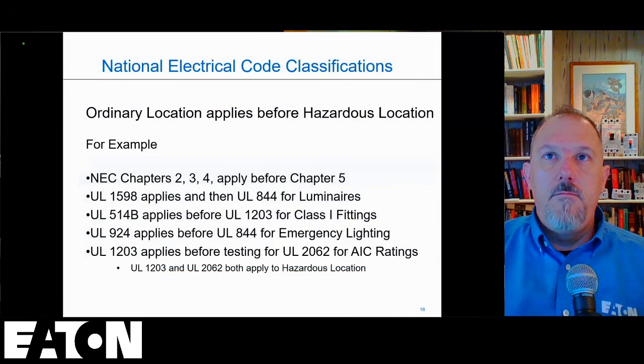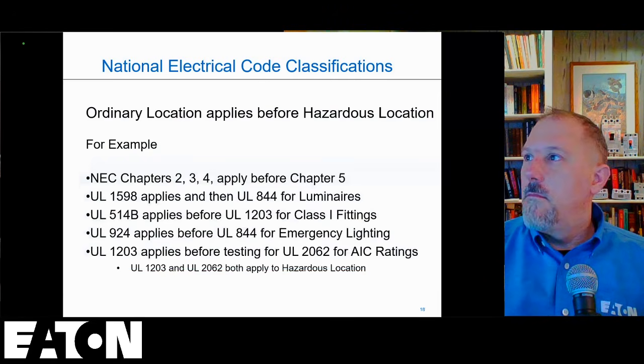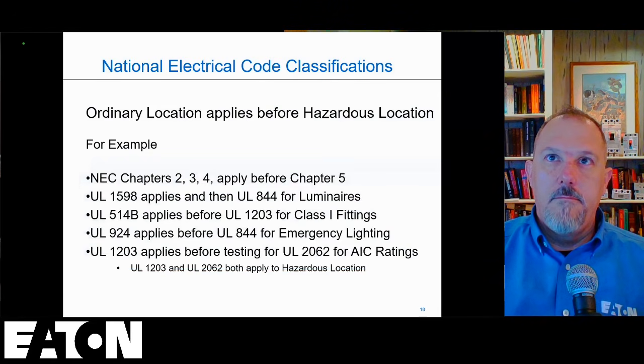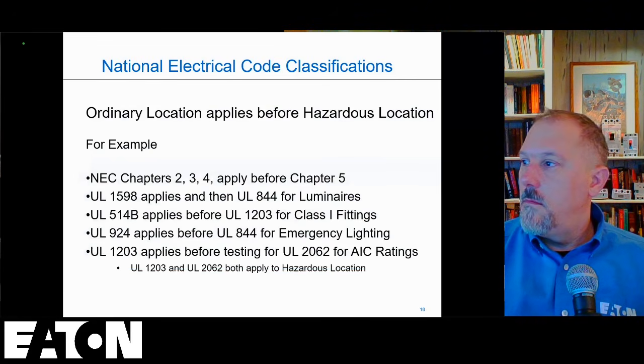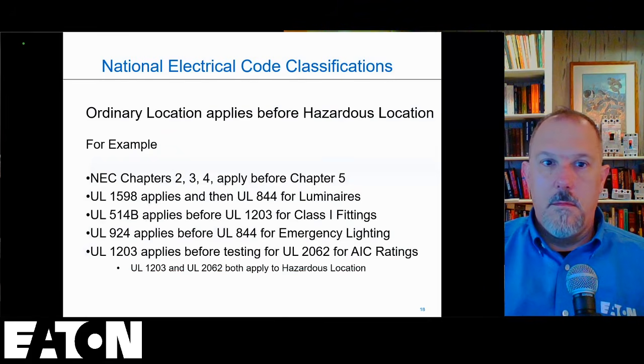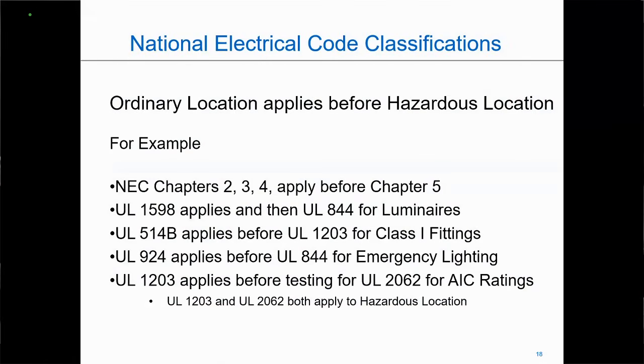Alrighty. So as we started to allude to a moment ago, and whoever asked that question as far as the lockout, tagout, and everything, it was a perfect setup for this slide. Everything that we do in Chapter 5, the hazardous location articles, the previous articles of the code, Chapters 2, 3, and 4, all apply. So Chapter 5 is an extension of those particular code articles of what we need to do in addition for hazardous location areas. But everything in those first chapters still applies. And the same thing happens when we're testing and having equipment certified for hazardous location areas. All the ordinary location tests have to be done first, and then the hazardous location tests are an extension of those ordinary location tests.